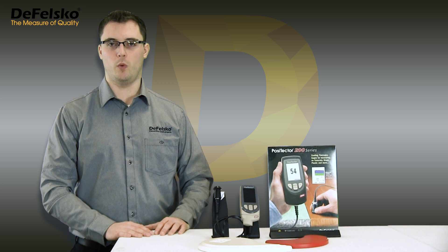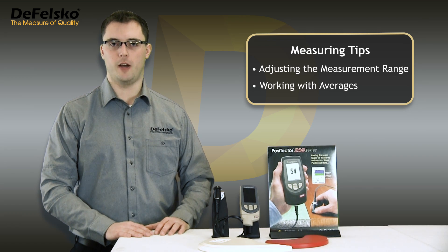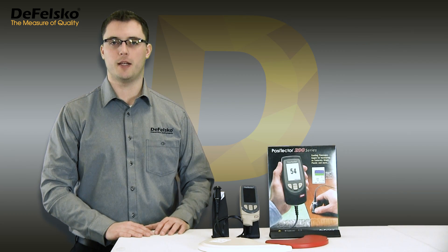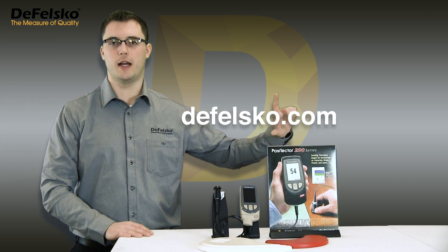To recap, when measuring on rough surfaces, raise the low range value to not more than half the expected coating thickness, and use memory to average a series of measurements. These two simple steps will provide meaningful thickness measurement results on coatings with rough surfaces. For more information about the Positector 200, visit defelsko.com/200.